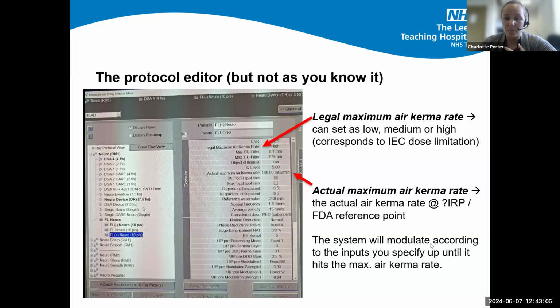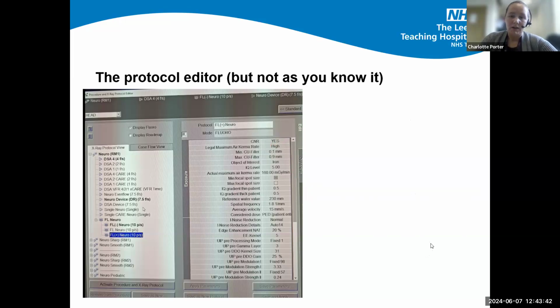But essentially, the system will modulate up to that maximum air kerma rate, at which point it shouldn't go any higher. I think anecdotally, I've heard that for thinner patients the system's quite good and the doses can be quite low, but the system has the ability to give quite high doses for larger patients. So that might be something to be aware of. Obviously, we're using the system in neuro, so there's only so much variation you get with heads. But for those of you who are going to be using it for more general purposes or in cardiac, it might be something to be aware of.